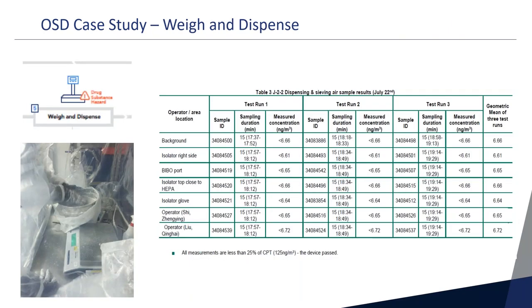Starting with the weigh-and-dispense process — a unique process with added challenges since operators were also performing manual sieving of the API — the flexible film isolator delivered excellent results. Following the SMEPAC protocol of three test runs, the geometric mean containment was less than seven nanograms per cubic meter. This is an excellent result when handling drug substance at this point in the process.